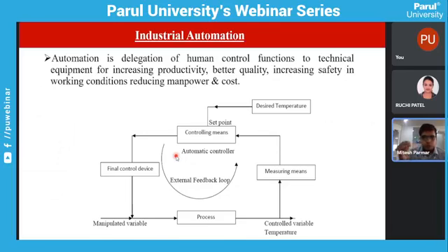In this automated controller, we have put some program as per our requirement, which has our desired set points. Like, this is my process to maintain the temperature of 500 degrees Celsius. That type of program I have put in this automated controller. So what is the working of this automated controller? It will receive the temperature sensor signal. For example, right now it is receiving 400 degrees Celsius from the temperature sensor, and my set point is 500 degrees Celsius. So your automated controller will find that your process value, which it received via the sensor, is less than your set point.